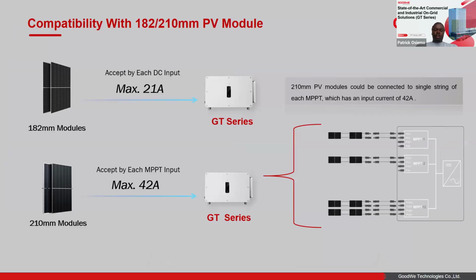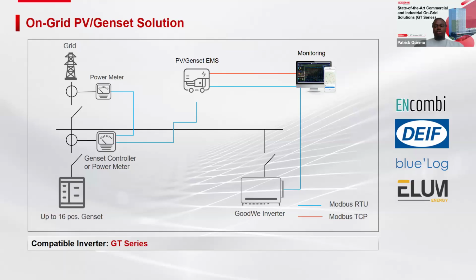The next application scenario is with the PV panels. What we've noticed is that PV panels are increasing in rating and efficiency. The GT series has the capability of allowing up to 21 amps per string. This is basically 42 amps for every MPPT. Each MPPT has two string inputs. This rating allows you to connect bifacial high power panels to the inverter and even oversize the inverter, making it comfortable to accommodate the latest panels, even the old model panels. That is the high tech that we've done with the GT series. High power panels still connect with the GT series.